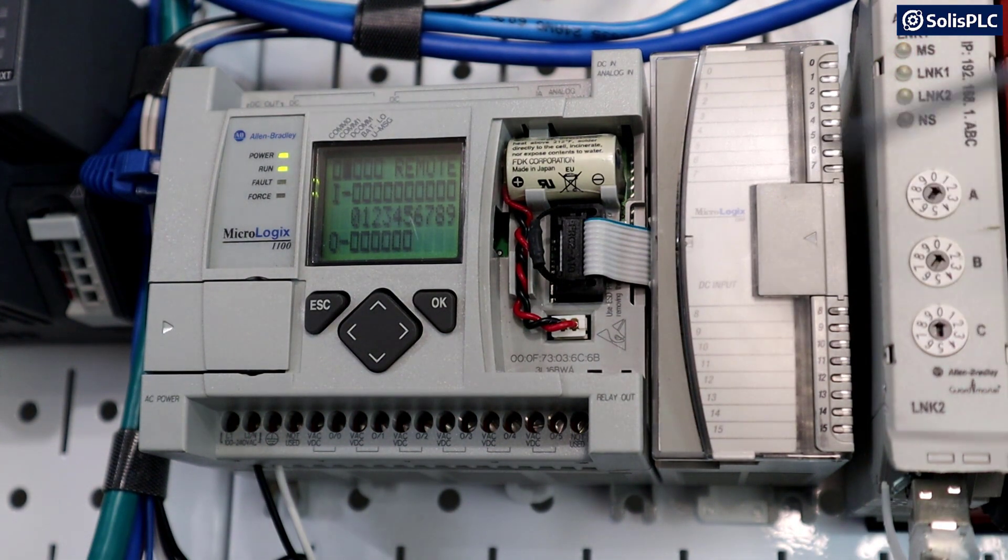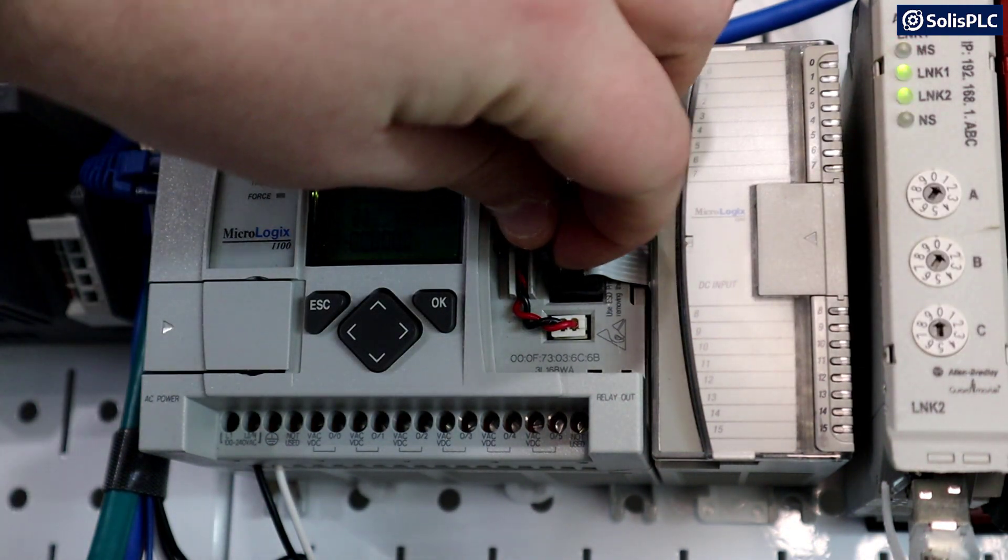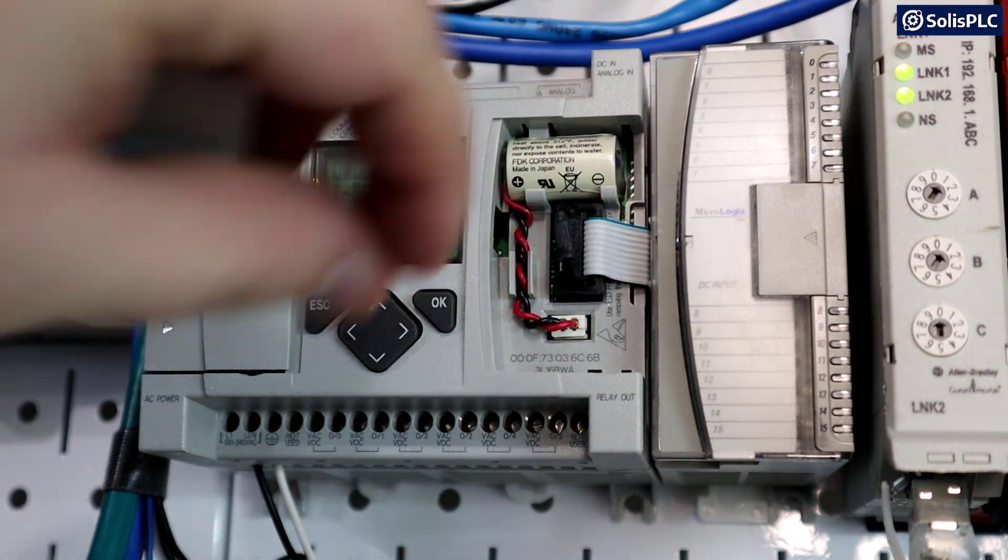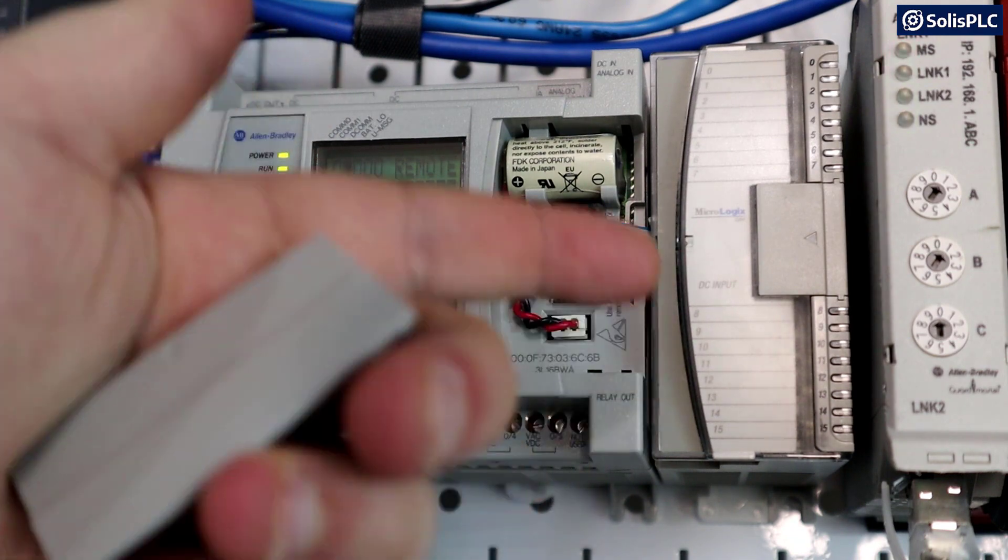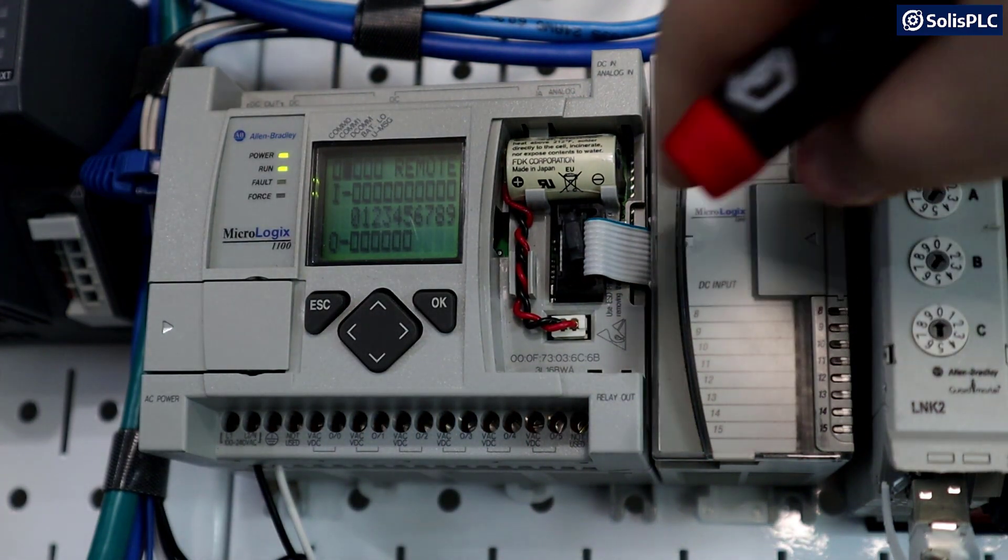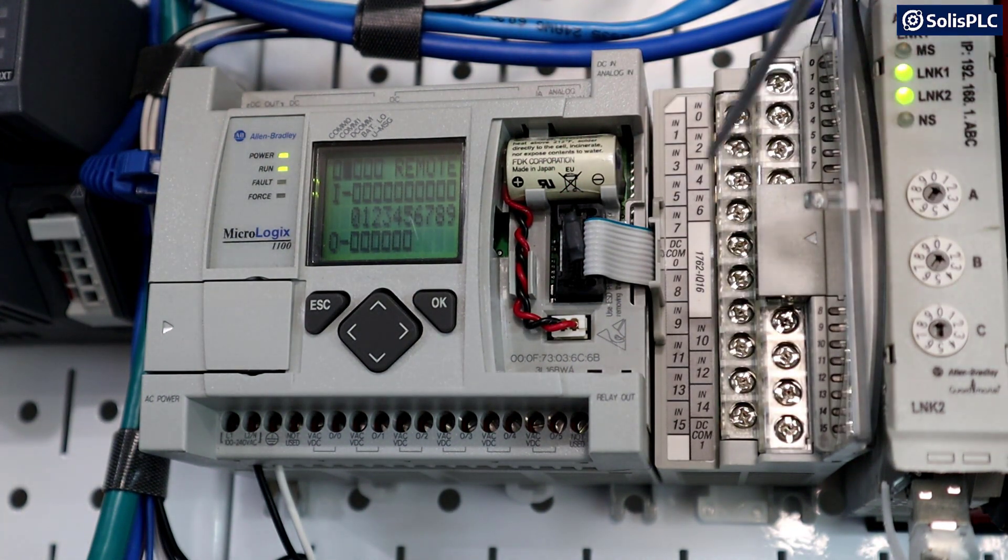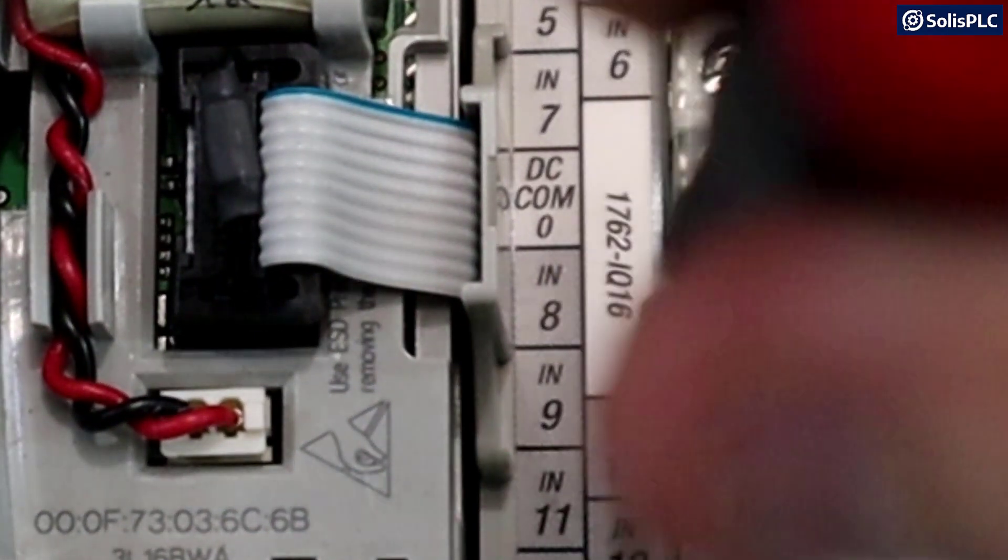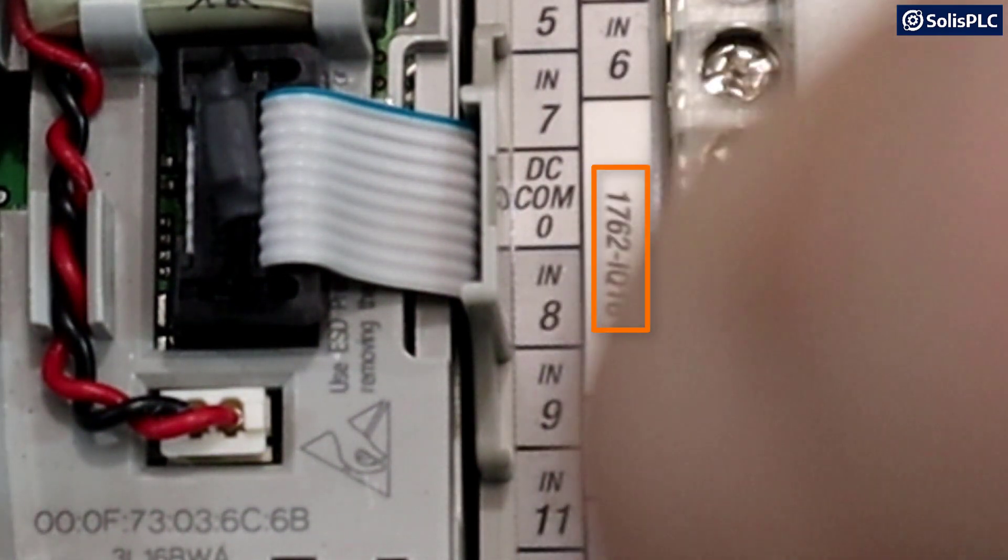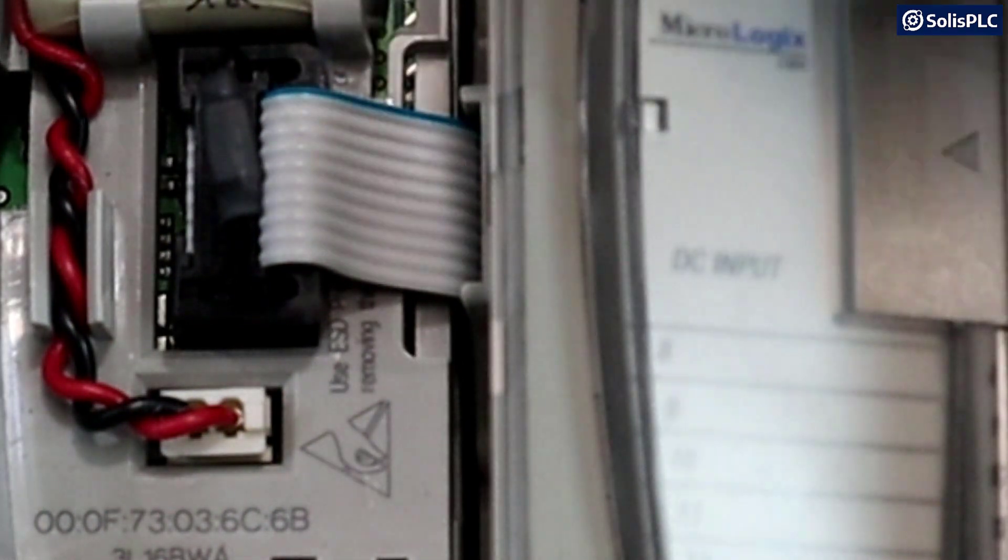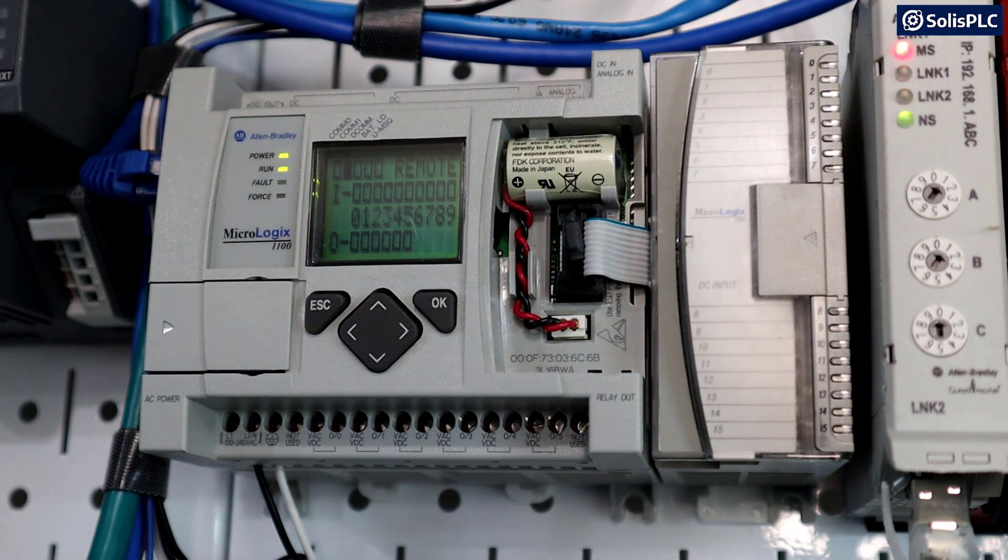That being said, to connect the I/O card, you're going to plug in this ribbon cable and you've got this little convenient type of handle that you can use to pull out this connector. Once you power down the PLC, you can remove this and remove the I/O card. But in order to connect it like we've done in this case, you're going to plug it into that socket. Now, the next step is, unless you already know the identification number of your card, it is going to be looking at the side panel here or on the back where the part number is going to be written. But it is a 1762-IQ16, which is a 16 input DC card.